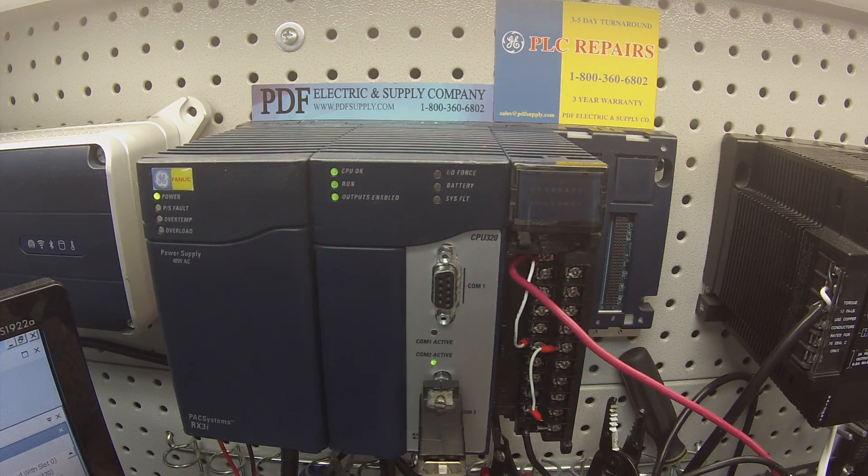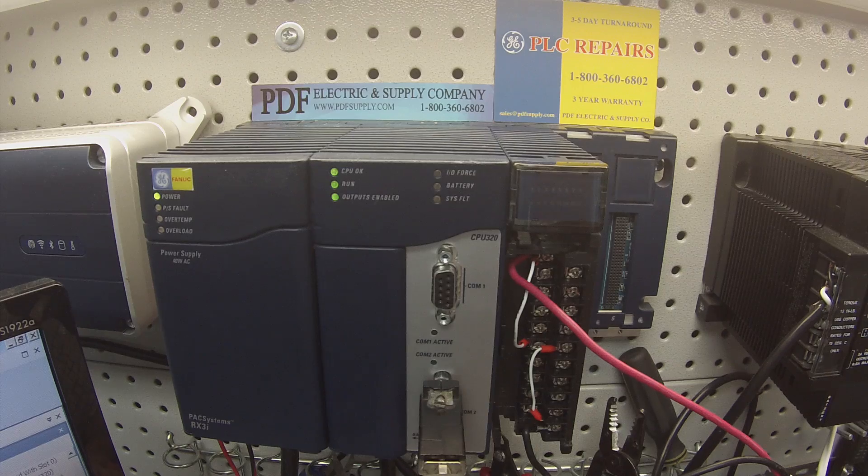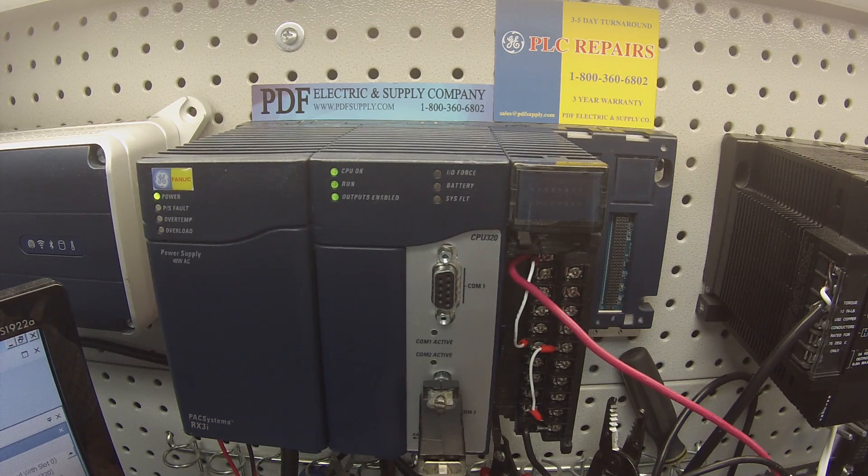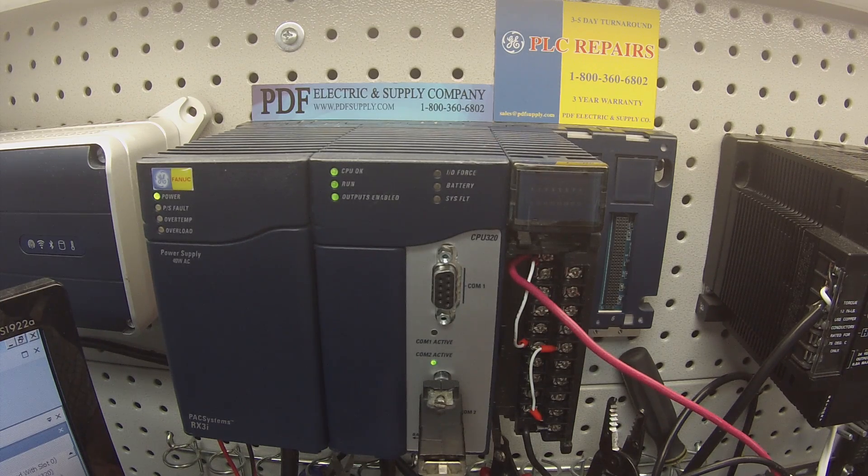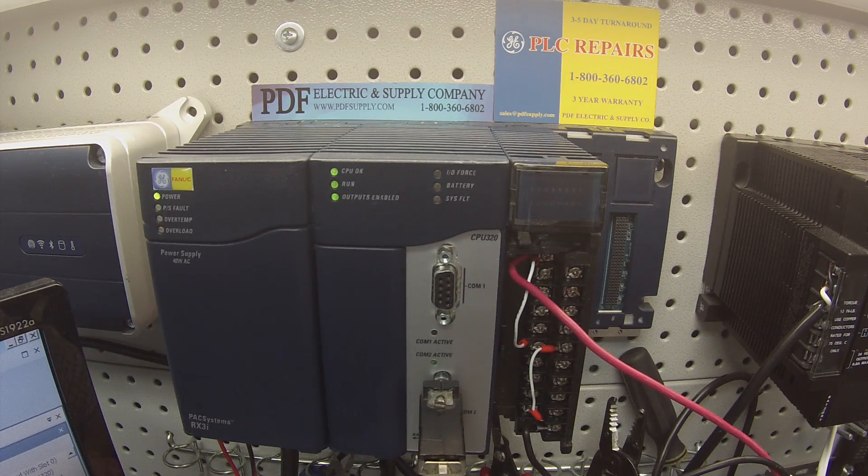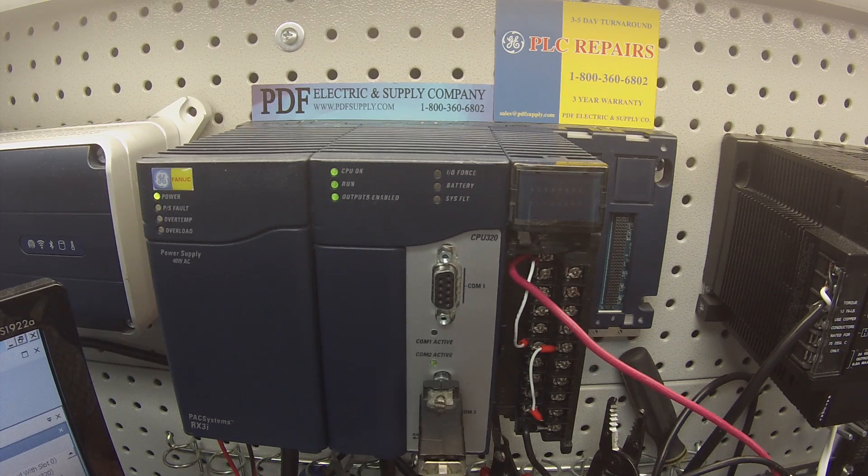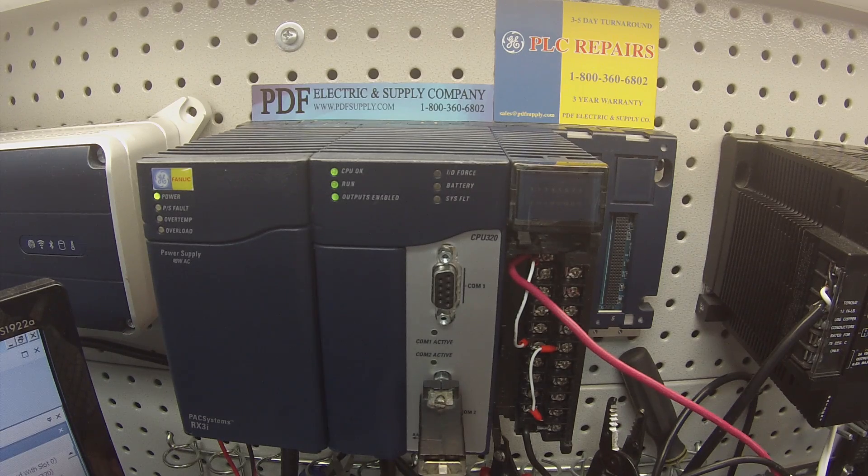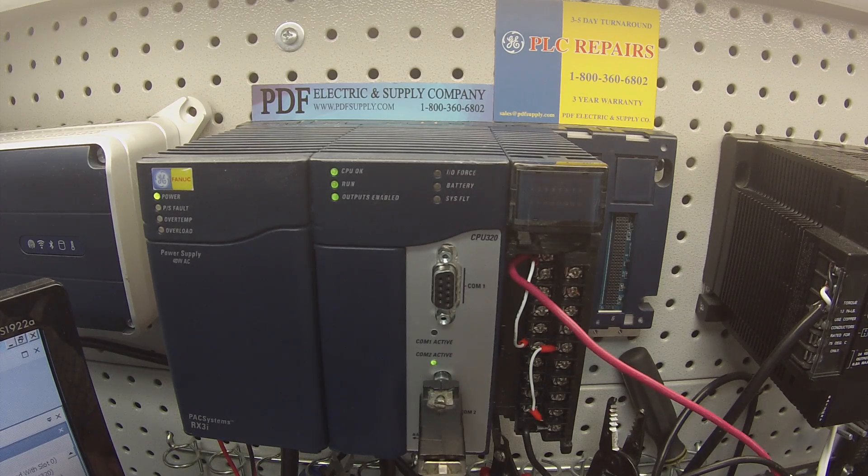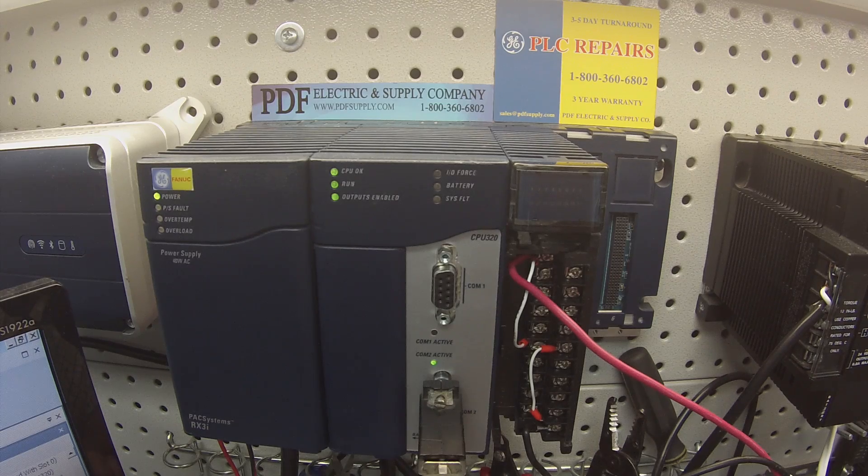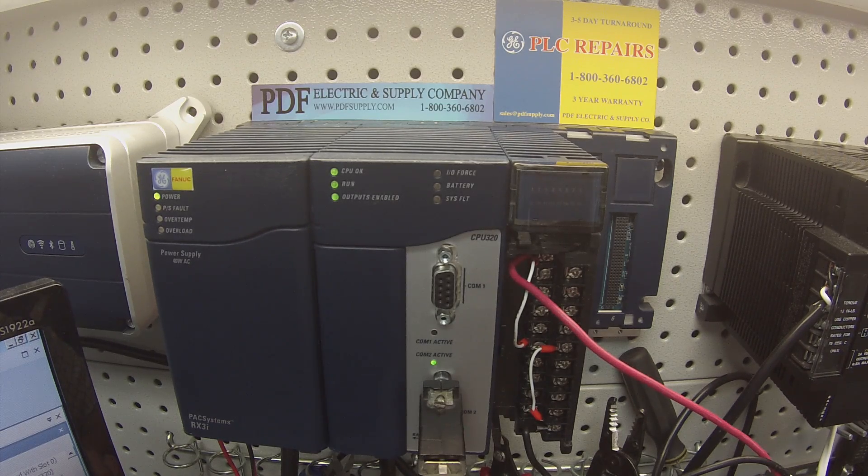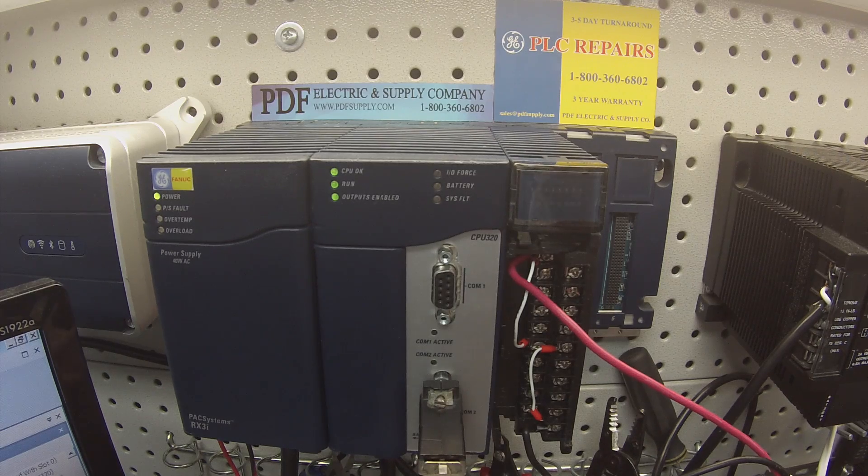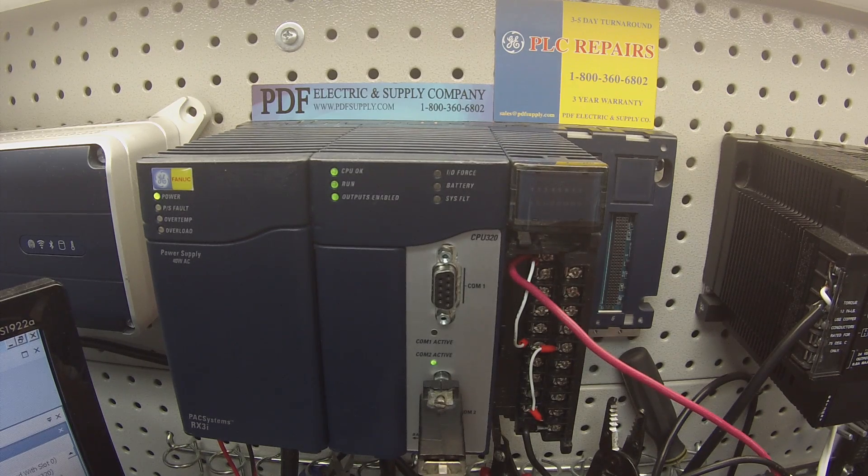Just to recap, problems that you'll find with this particular card is you'll turn a channel on and the LED that's associated with that particular channel doesn't turn on, or it's in the on position and the LED is on but you don't have any power going through it, or it's in the off position and it's technically still on if you touch a probe to it. Any of those things are a card failure and they need replacement or repair.